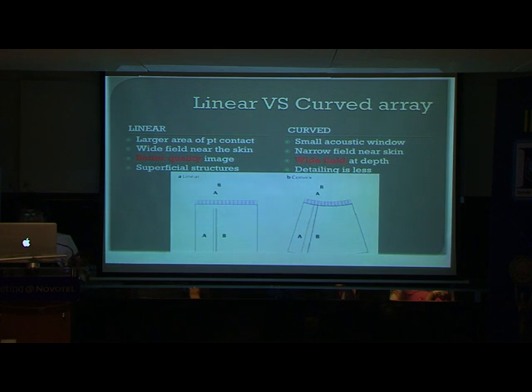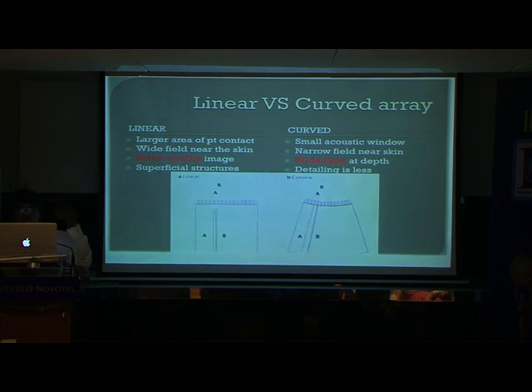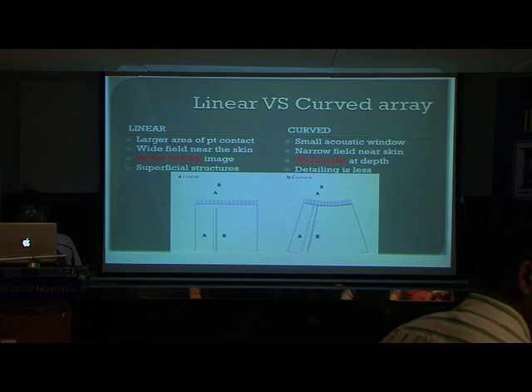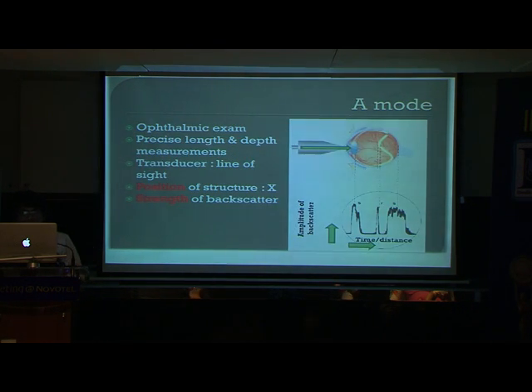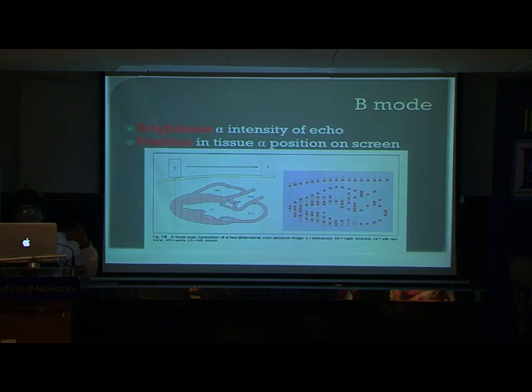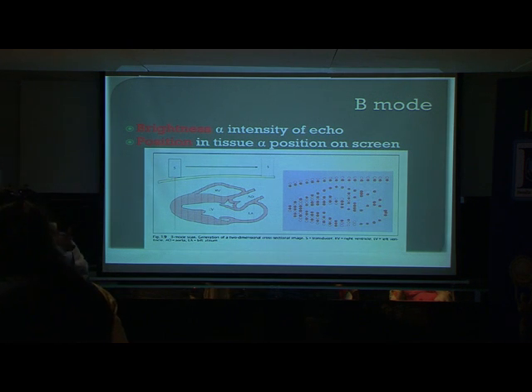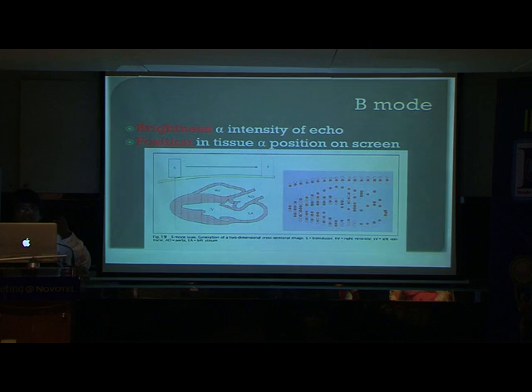Selection of linear versus curved array probe: linear array probes are high-frequency probes for near-field imaging; for interventions at a deeper level, a curved probe with lower frequency is preferable. For our purposes, we use brightness mode (B mode). The image is displayed as an ultrasound beam passes through various tissue densities, which reflect echoes back, creating a grayscale image in 256 shades of gray on the monitor. Cardiologists use M mode for fast-moving structures like the heart, timed with the ECG.